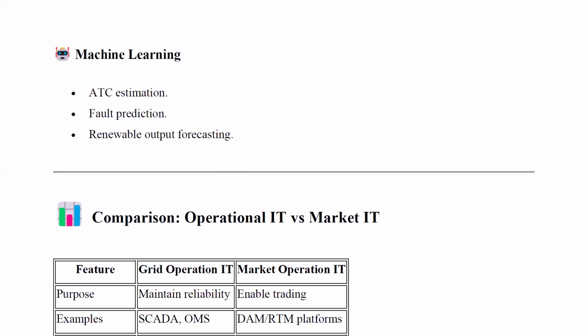Fault prediction estimation is also possible. If a line-to-ground fault happens, what will be the current change? If a line fault happens, what will be the current? For a triple line-to-ground fault, what will be the current? Based on that, you can simulate, so if the current rises suddenly, you can easily identify which kind of fault it is, and send your workers to that particular place, making fault identification and rectification very easy and fast.